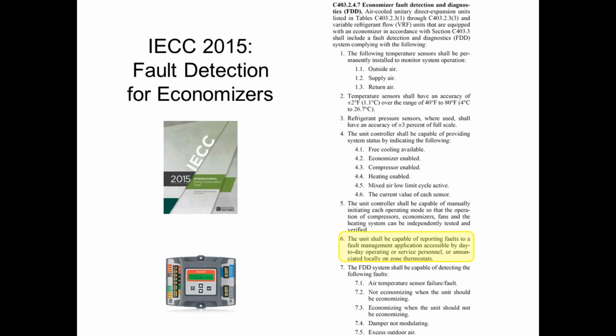The one thing that makes it kind of interesting is item number 6. I'm going to read it to you, even though I'm not going to read code to you today for the most part. I'm going to read this line. The unit shall be capable of reporting faults to a fault management application, like a building automation system type thing, accessible by day-to-day operating or service personnel, right? So I can't have the screen on the economizer controller that's locked in the rooftop cabinet be my monitoring system. It cannot, because that is not accessible to day-to-day operating or service personnel.